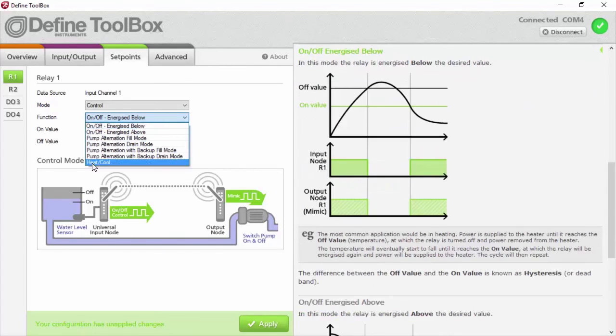So we do have heat and cool modes and all sorts of other modes in here, but the one we want today is the energized below, because when the water level goes below our trip point, we want to turn on the pump, and when it goes above a certain value, we want to turn off the pump. So on, off, energized below.